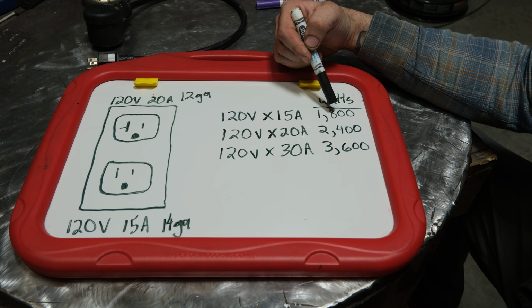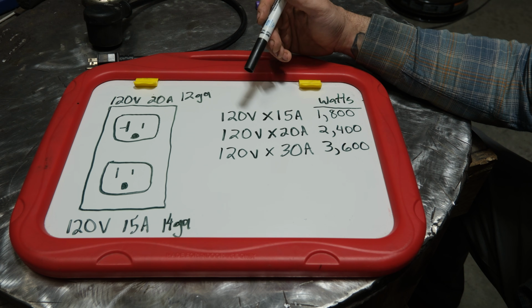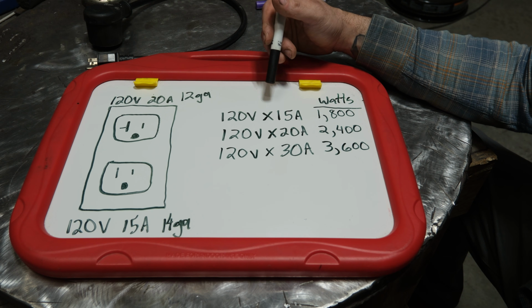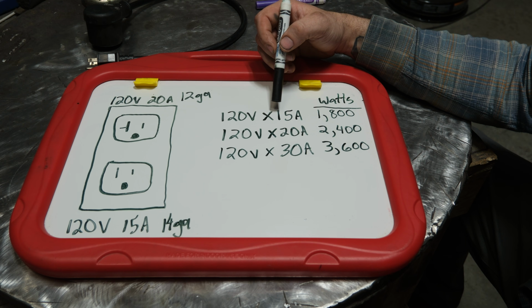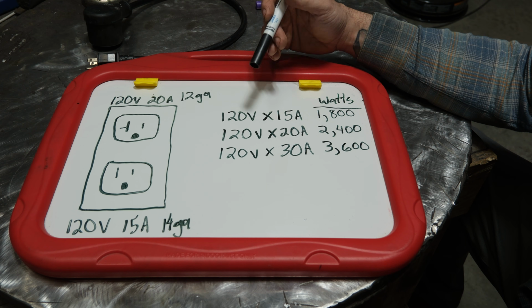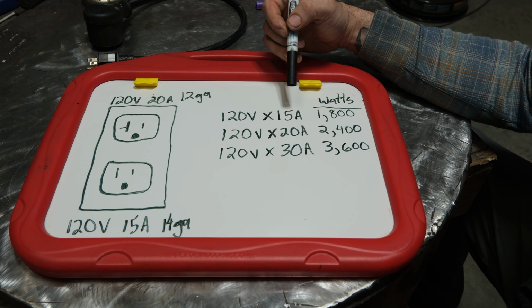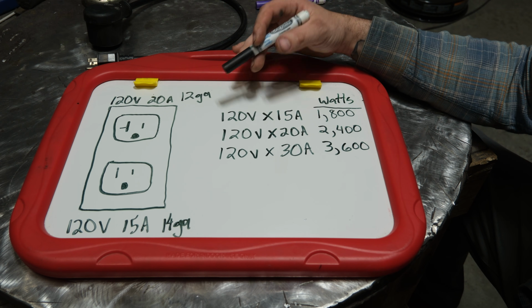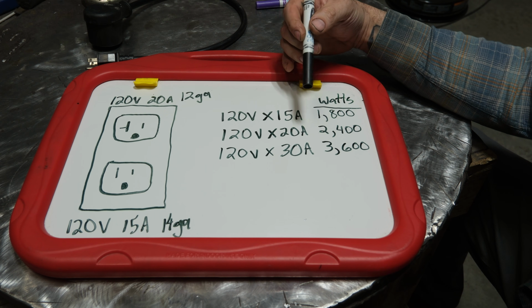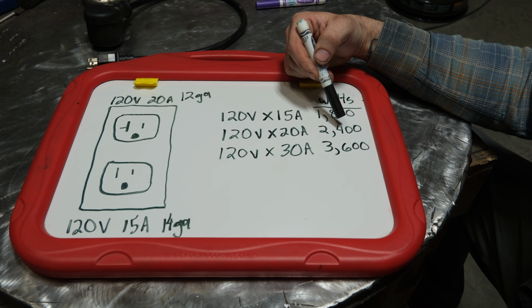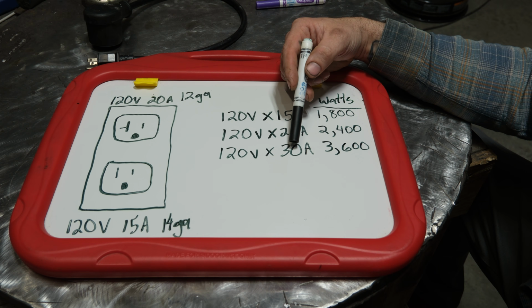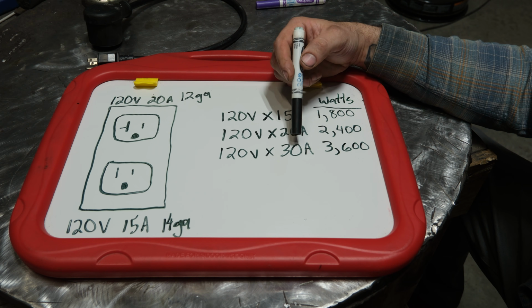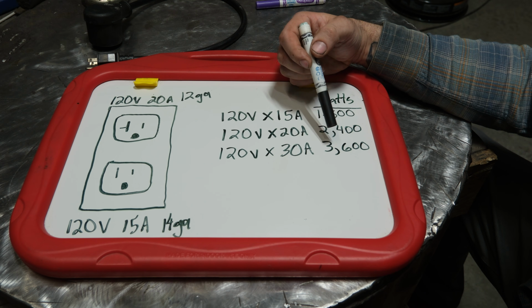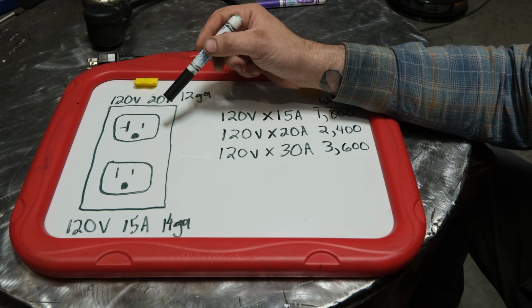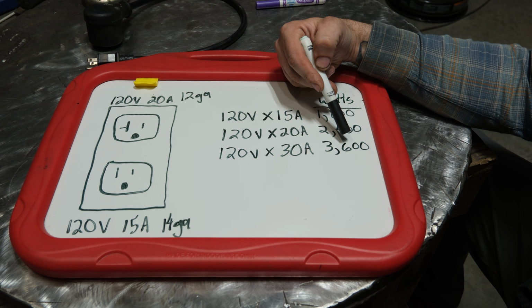Anything over this for an extended period of time will cause the breaker to trip, but welders are very intermittent use. So oftentimes with a 15 amp breaker, you might be able to get 22 to 25 amps while you're welding through that 15 amp breaker before it trips. I'll talk a little bit more about that later, but for right now, we're just going to go by face value ratings. So 1,800 watts, 2,400 watts for a 20 amp, and a 30 amp, which is pretty uncommon in a house. However, generators very commonly have a 30 amp 120 breaker and outlet. That does not look like this. That is a different style, but that's 3,600 watts.